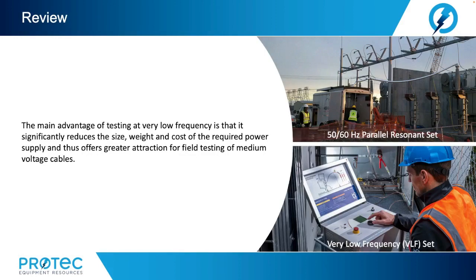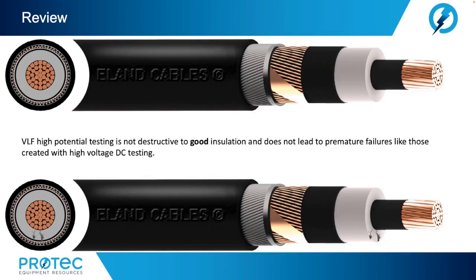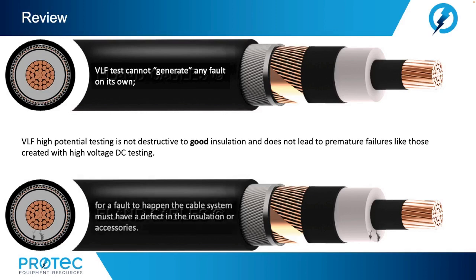So let's review. The main advantage of testing at very low frequency is that it significantly reduces the size, the weight, and the cost of the required power supply, and thus offers greater attraction for field testing of medium voltage cables. Also, VLF high potential testing is not destructive to good insulation and does not lead to premature failures like those created with high voltage DC testing, as we learned in part 1 of this cable testing series. VLF tests cannot generate any fault on its own.